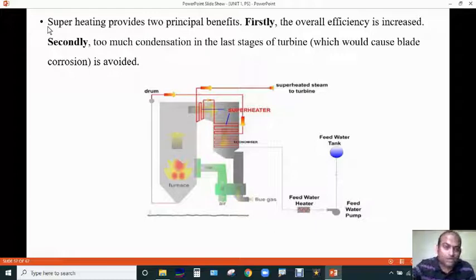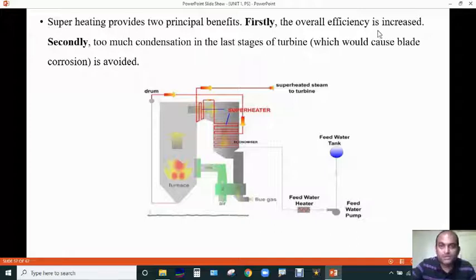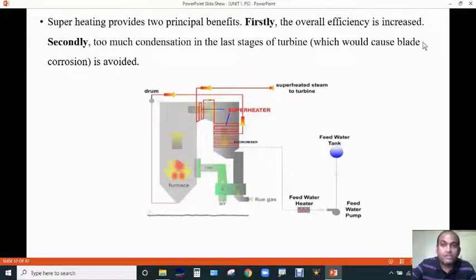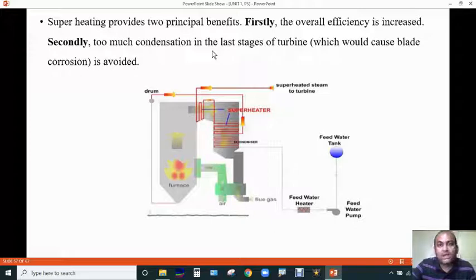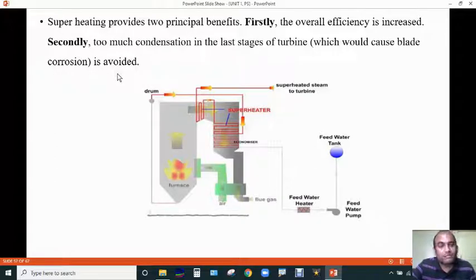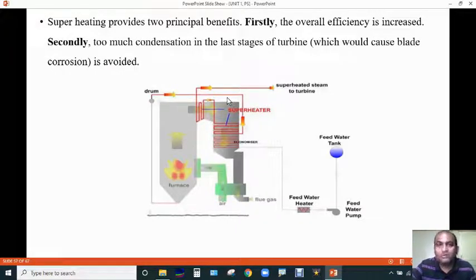What is the function of the superheater and what are the benefits? The first benefit is that the overall efficiency of the thermal power plant is increased. Second, too much condensation in the last stage of the turbine would cause blade corrosion. So to avoid corrosion, we have to convert the wet steam into dry steam before passing it to the turbine.